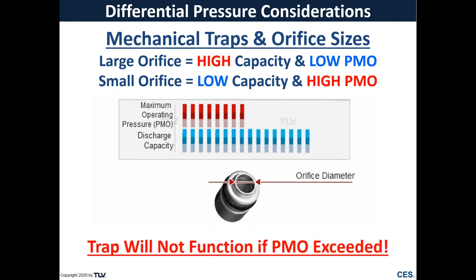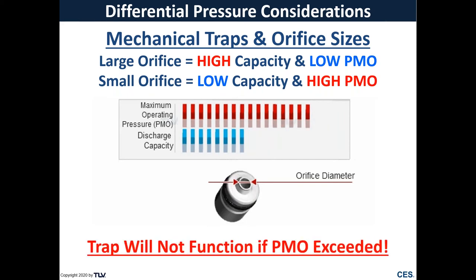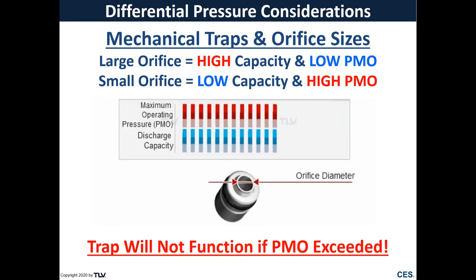Now, it's important to note that if we exceed the maximum pressure of that orifice, our trap will not function and will actually lock shut. So if we need more capacity, we're going to need to go to a larger trap rather than just going up to a larger orifice if we exceed the orifice pressure.